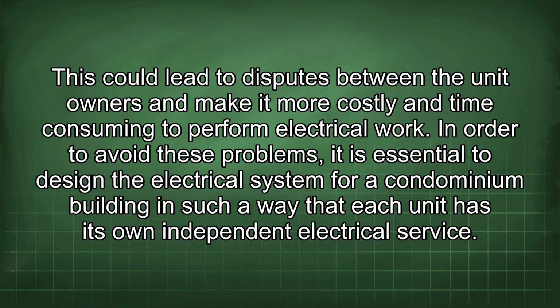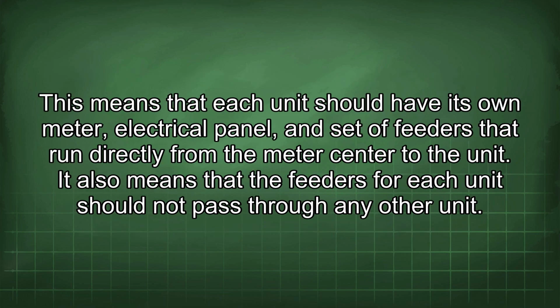In order to avoid these problems, it is essential to design the electrical system for a condominium building in such a way that each unit has its own independent electrical service. This means that each unit should have its own meter, electrical panel, and set of feeders that run directly from the meter center to the unit. It also means that the feeders for each unit should not pass through any other unit.